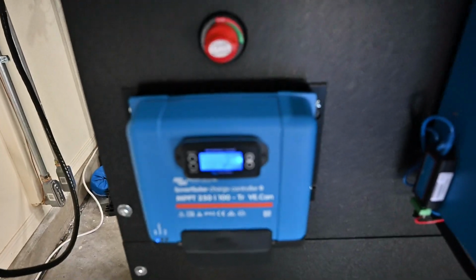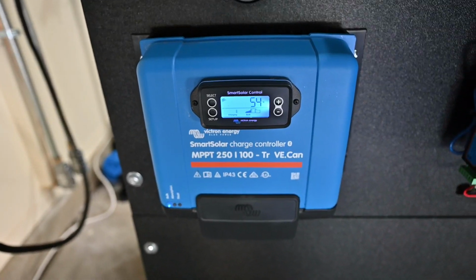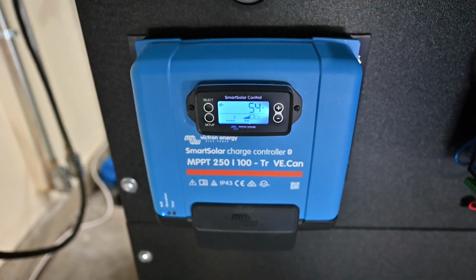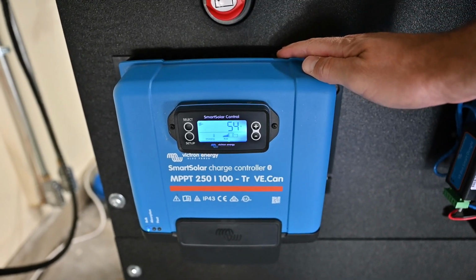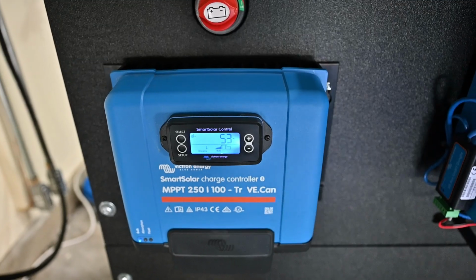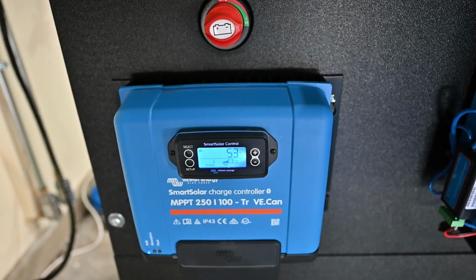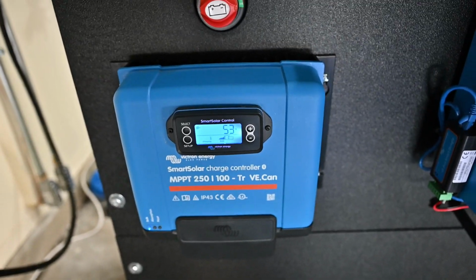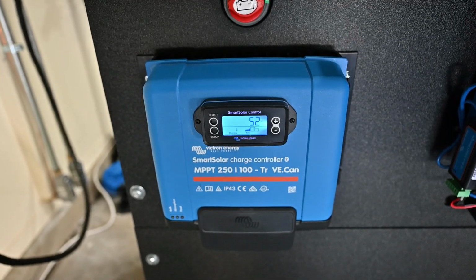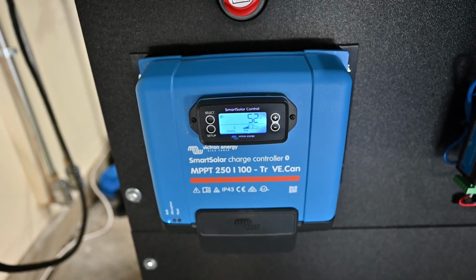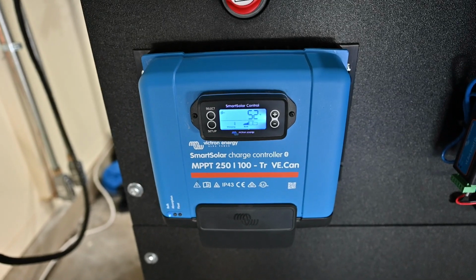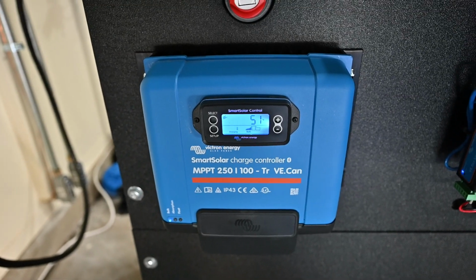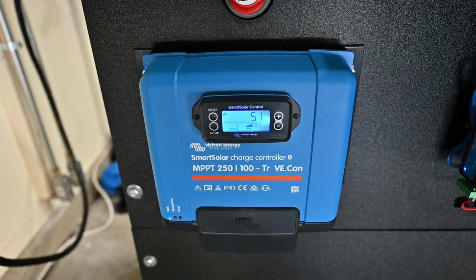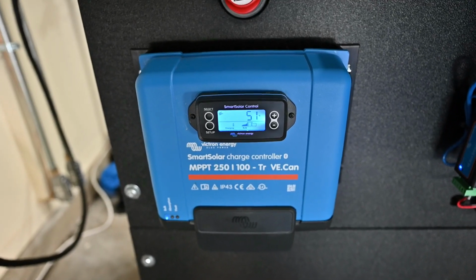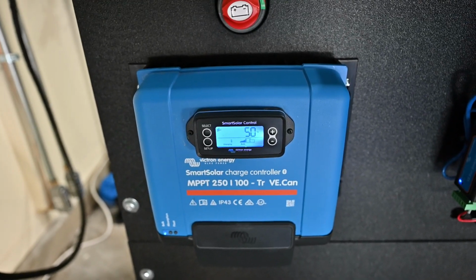I generally keep this fan plugged in. It's an AC fan, consumes 20 watts, and within a minute or so the temperature will start dropping, down to around room temperature. It's advertised that the charge controller is extremely efficient because it doesn't need a fan, but I've seen this thing getting up to 65C, and any kind of high temperature isn't good for electronics, so I go ahead and cool it with a fan.